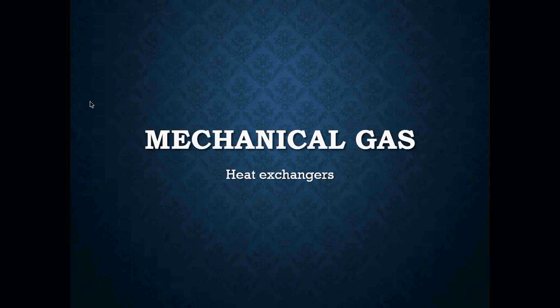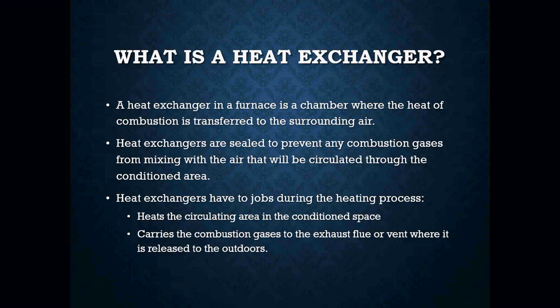Because if we miss something in a heat exchanger, we honestly can do harm to the people and the occupants that are actually using this device. So the heat exchanger in a furnace is a chamber where the heat of combustion is transferred to the surrounding air. Heat exchangers are sealed to prevent any combustion gases from mixing with the air that will be circulated through our conditioned space. Heat exchangers have two jobs during the heating process.